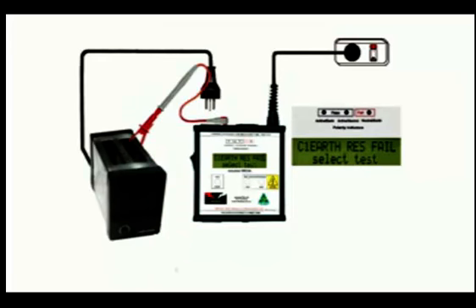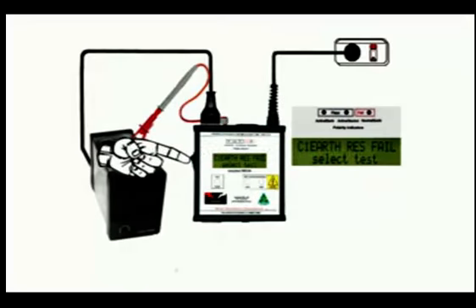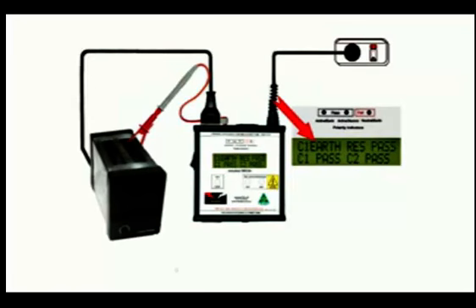So firmly clamp the earth probe onto any exposed metal we can find, check that the appliance and the Mega are both switched off, and plug the toaster into the top socket of the Mega. Switch on the EASYTEST Mega, and immediately we see that the earth resistance is tested and passed. And on the bottom line we have a Class 1 pass, indicating that there's no leakage current, or if there's any, it's below the 5 mA safe level set by the Australian standard.